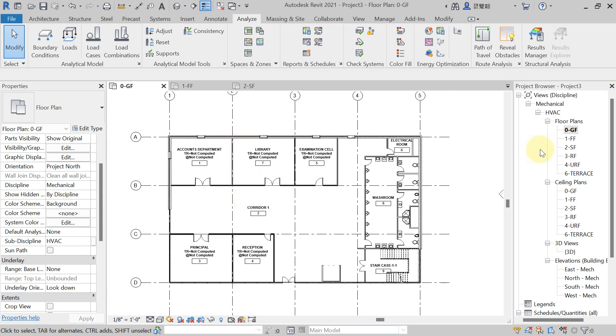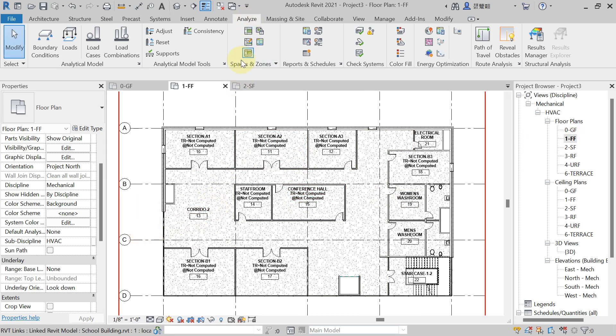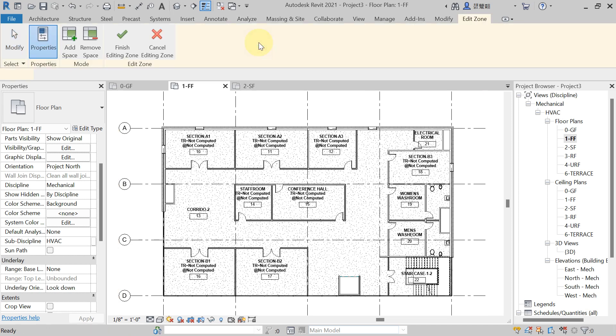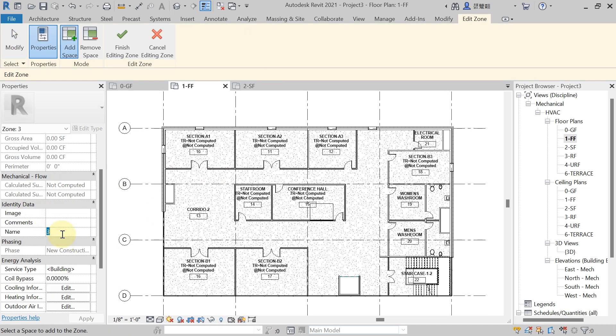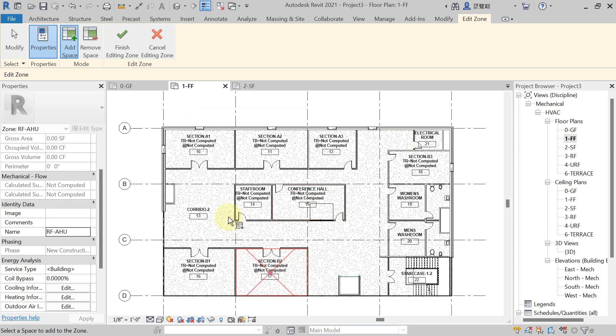Now come to the first floor. Here also we have to create the HVAC zone. Go to Analyze tab, Spaces and Zone panel, and hit on Zone. In the Properties palette, give the name — I'm using the same name 'RF AHU' since it's the same AHU. If you were using a separate AHU for each floor, you would write AHU1, AHU2, etc. Since I'm using the same name, you will get a warning: 'Element has duplicate name values.' Hit OK to proceed.